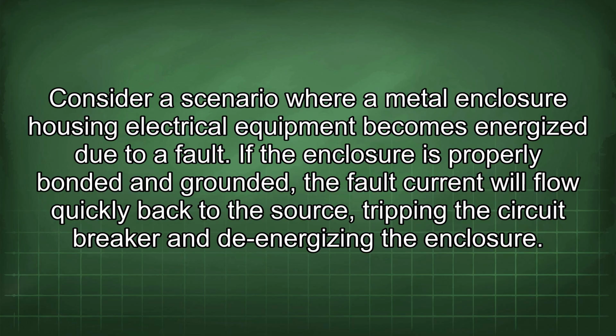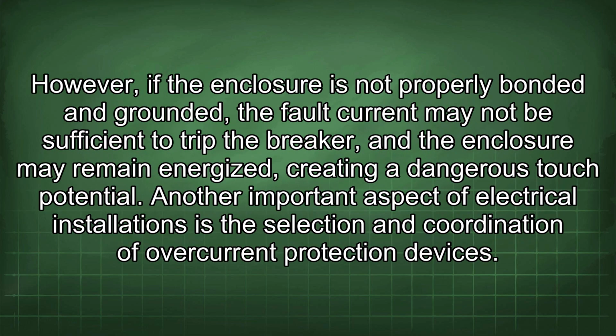Consider a scenario where a metal enclosure housing electrical equipment becomes energized due to a fault. If the enclosure is properly bonded and grounded, the fault current will flow quickly back to the source, tripping the circuit breaker and de-energizing the enclosure. However, if the enclosure is not properly bonded and grounded, the fault current may not be sufficient to trip the breaker, and the enclosure may remain energized, creating a dangerous touch potential.